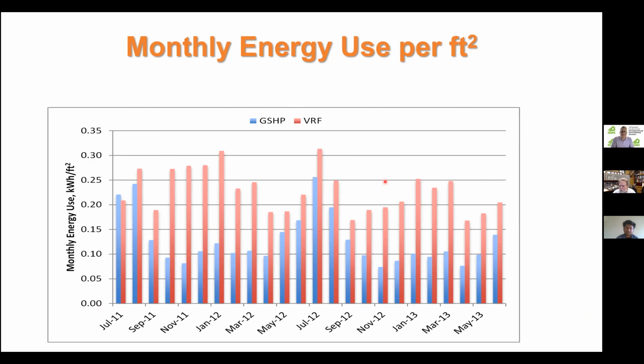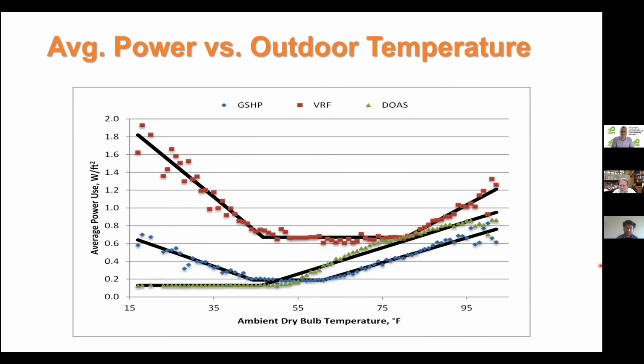Again, depending on the loads, maybe there's an explanation for that, but we'll come to that. Some of the results I'm going to show you are what we call a binned analysis, where, say, these points would represent the VRF system energy consumption in watts per square foot for all the hours between maybe 54.5 and 55.5, or I think we might have had slightly smaller bins, maybe 54.75 and 55.25. And this black line is just a fit to the data. You can see that at cold temperatures the VRF system uses about 3 times the electrical power of the ground source heat pump system. As it gets warmer, it uses less electricity, and there's maybe a shoulder region where it's at a minimum value for energy consumption.